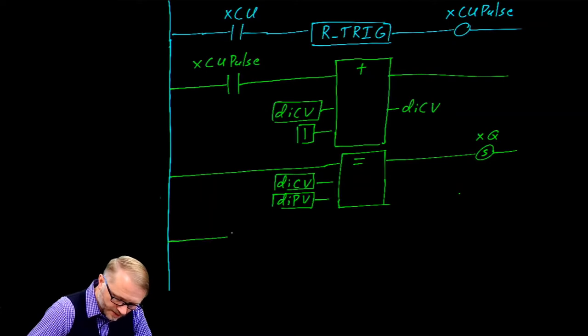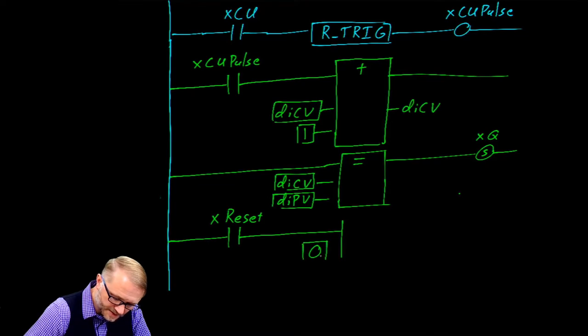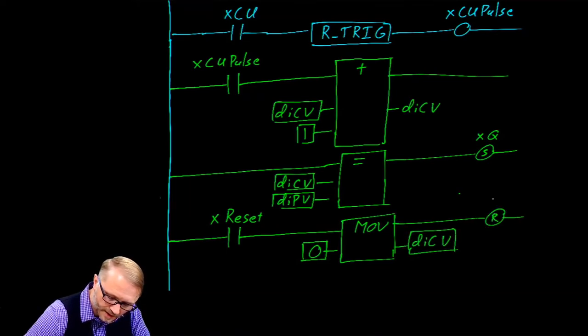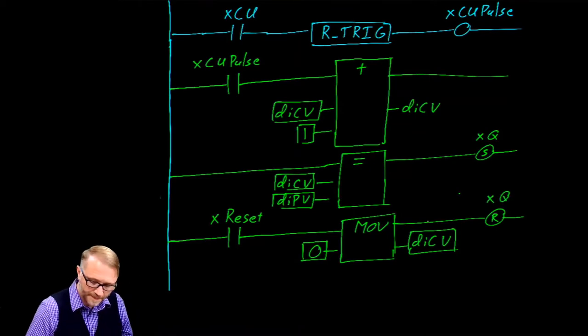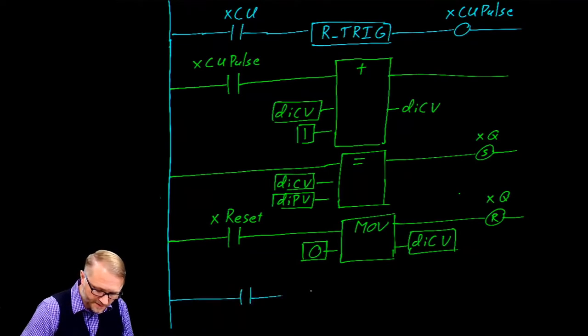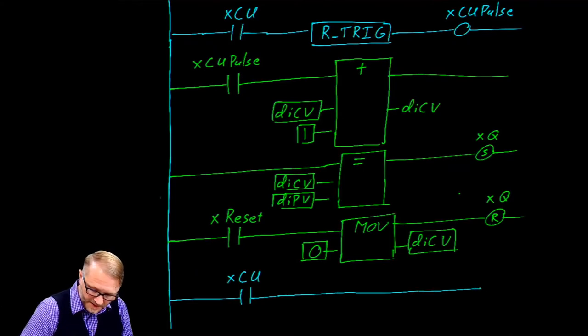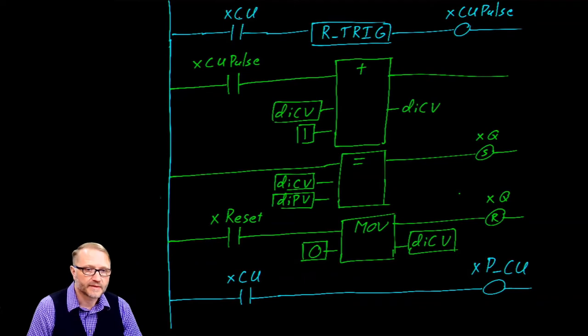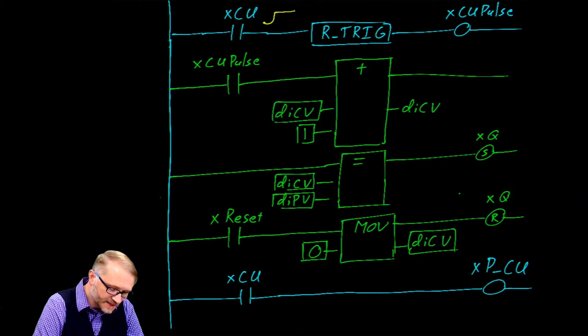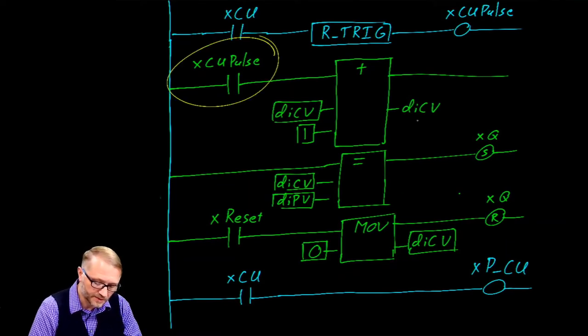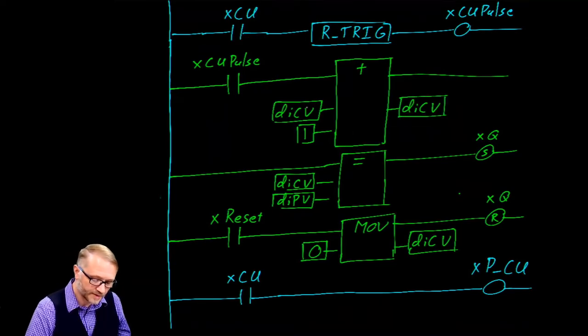The next rung is very simple — it's our reset rung where we move the value of 0 to memory location current value and reset our Q. Remember that the input and output of a move instruction — those lines are connected together. The last rung of the counter takes the value, the boolean count up, and places it into the boolean previous count up. Now let's see how we did. When we have an event — a rising edge on count up — there will be a pulse. If there is a pulse, we will increment the count by 1. We read the current value, modify it by adding 1, and write it back to current value.